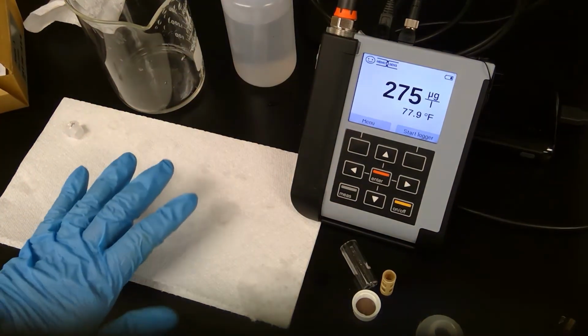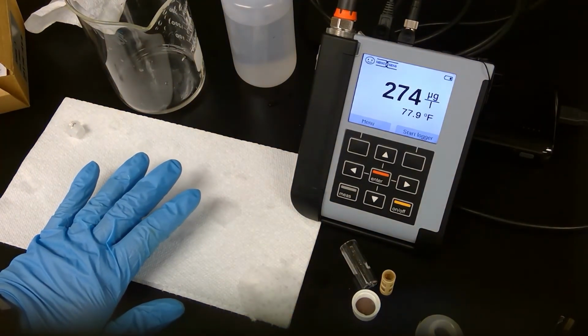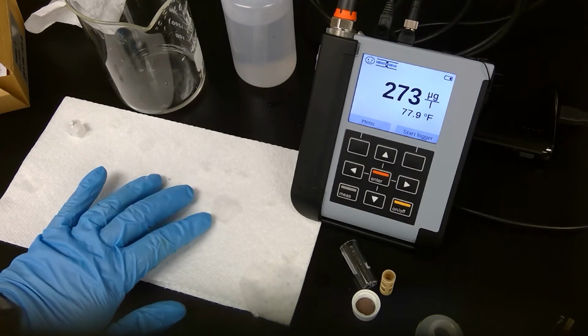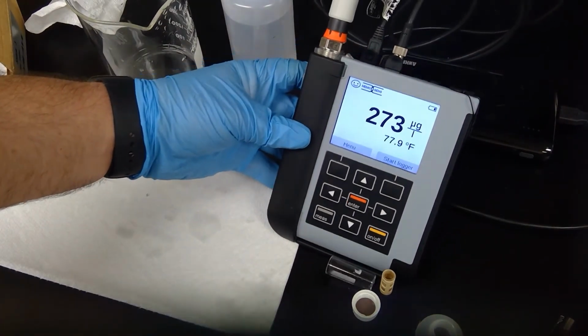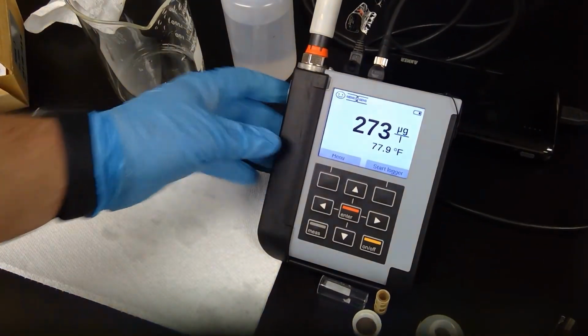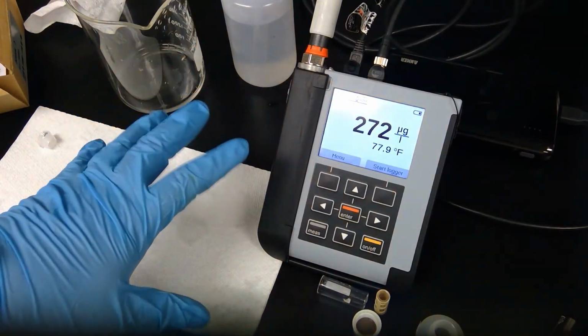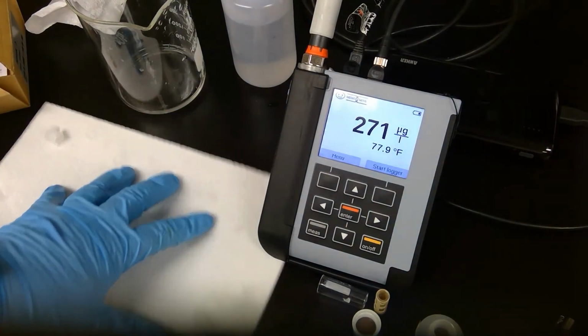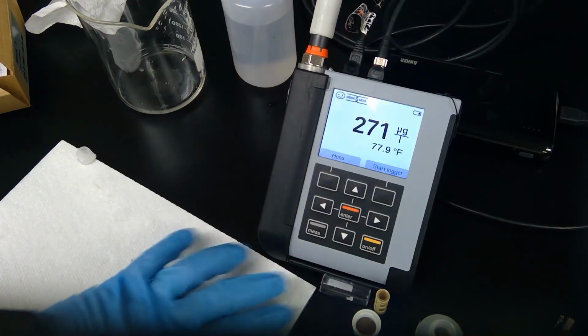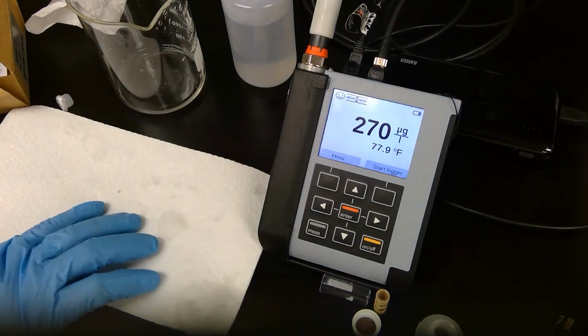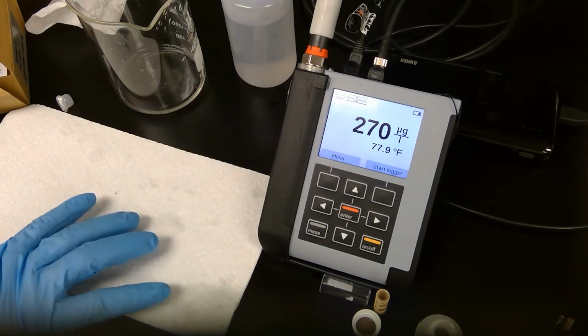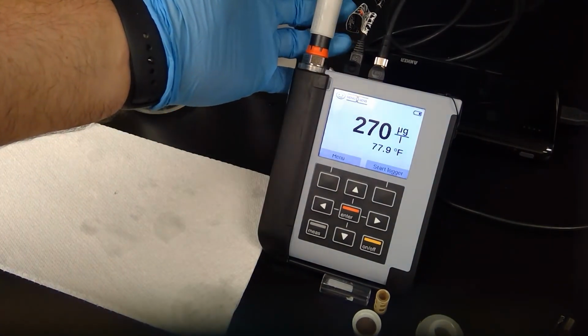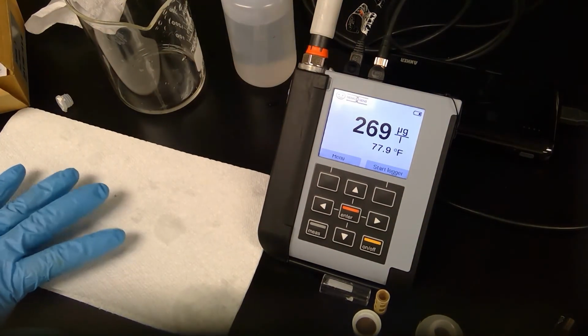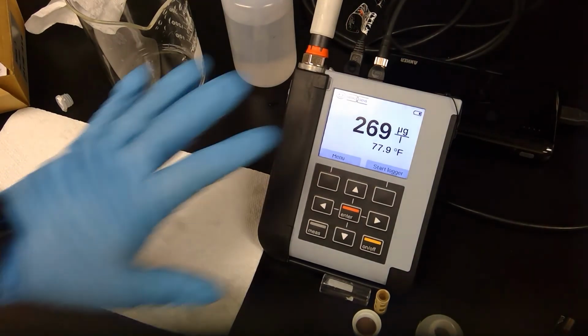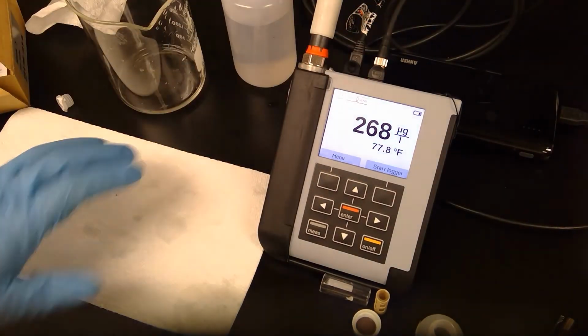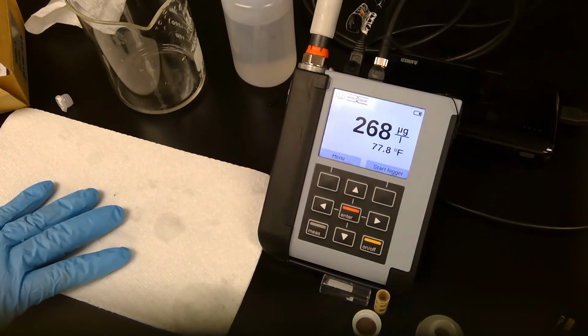Now, we would do a calibration next, and that's going to be for a different video, but what I want to make sure you understand is whenever you have an amperometric Clark cell style DO probe disconnected from a power source for any length of time, you've got to make sure you repolarize the sensor. What that means is you have to connect it to a power source for a period of time. So rule of thumb is leave it connected to the Portavo or transmitter or Memo Suite, if you're using Memo Suite, for 6 hours.